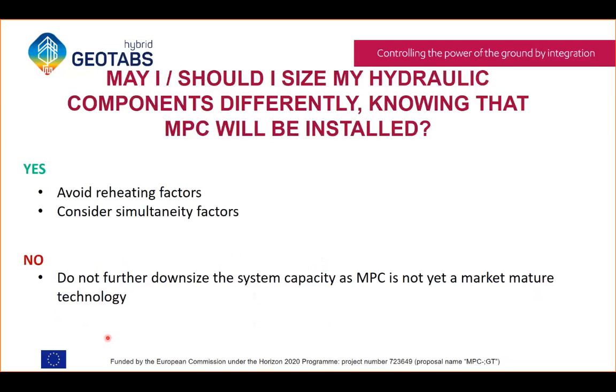Firstly, MPC is very good at predicting the need of the building, so reheating factors could be avoided. A reheating factor is, for example, when you add additional power to your system so that a room can be reheated in 30 minutes. But MPC will be able to anticipate how long it takes to heat up the room and therefore start on time. So I would advise that reheating factors be avoided.